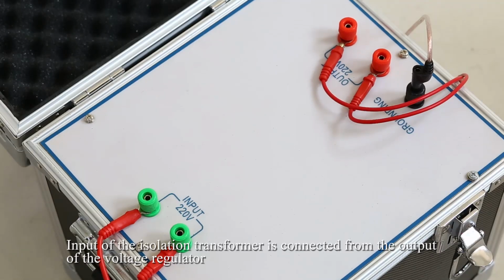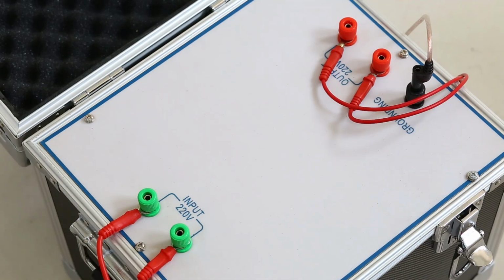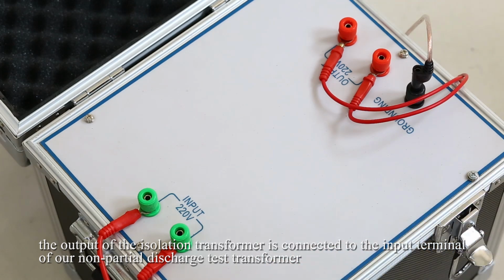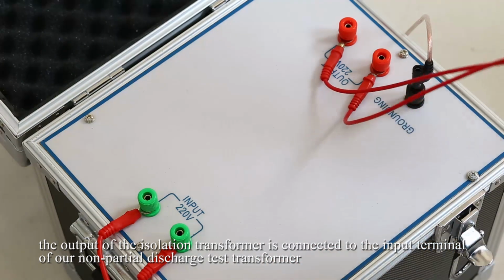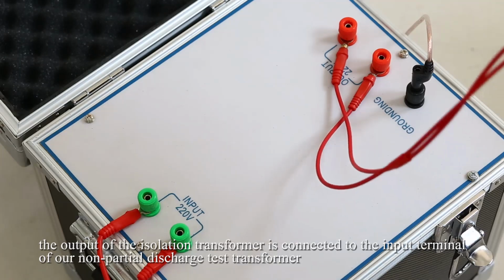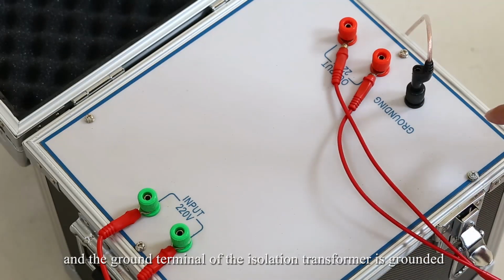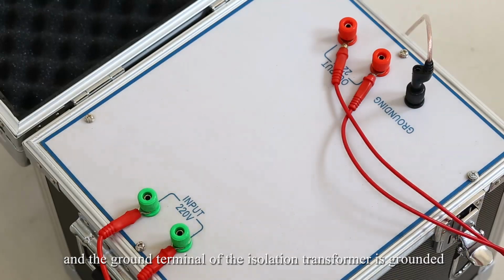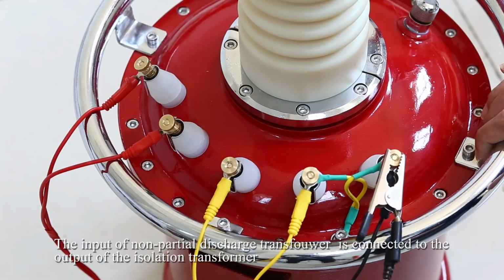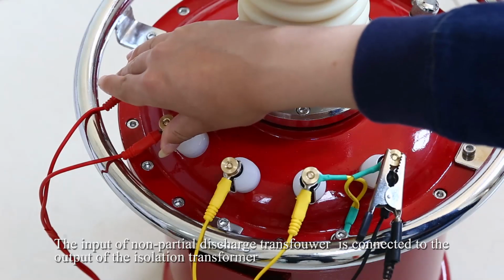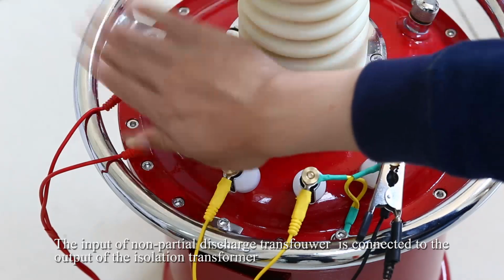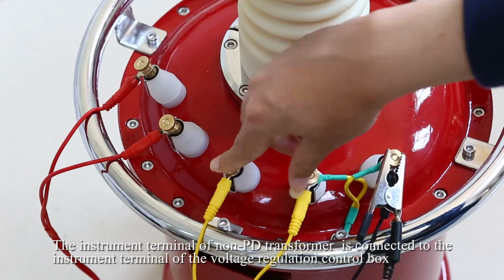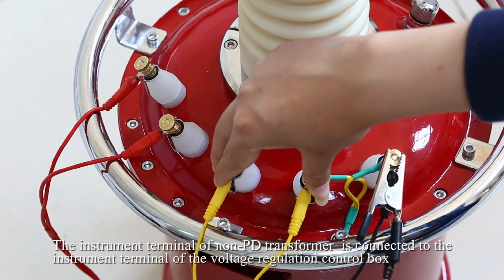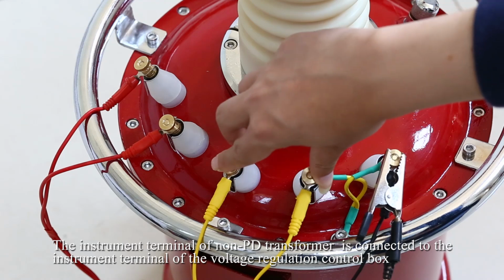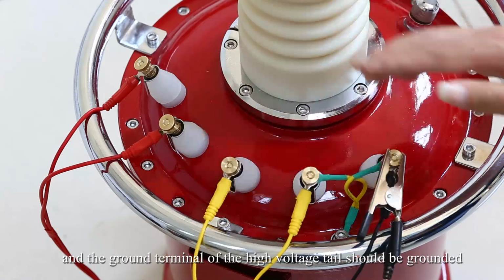The input of the isolation transformer is connected from the output of the voltage regulator. The output of the isolation transformer is connected to the input terminal of our non-partial discharge test transformer, and the ground terminal of the isolation transformer is grounded. The input of non-partial discharge transformer is connected to the output of the isolation transformer. The instrument terminal of non-PD transformer is connected to the instrument terminal of the voltage regulation control box, and the ground terminal of the high voltage tail to be grounded.